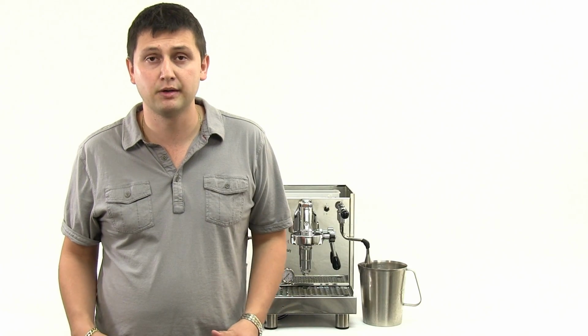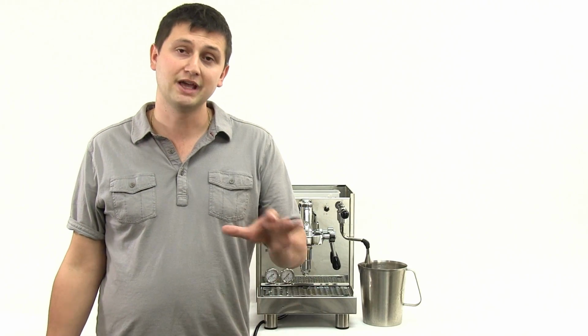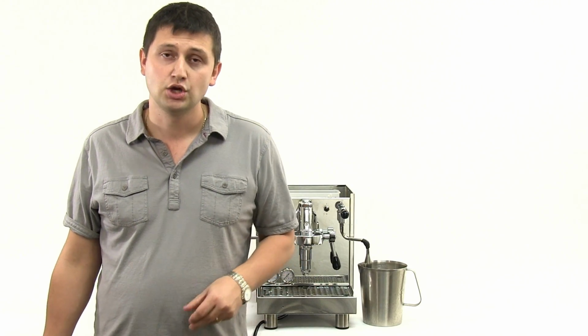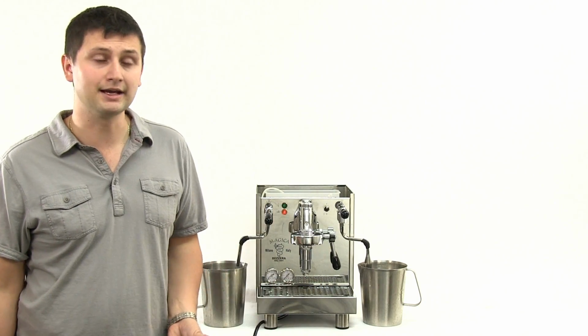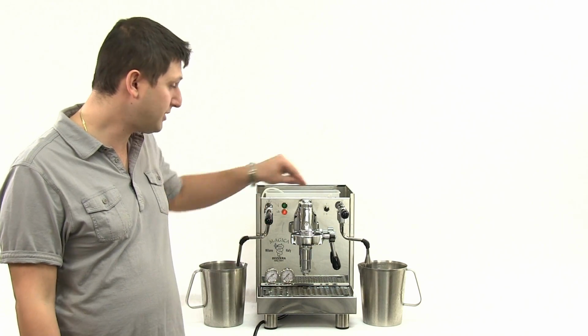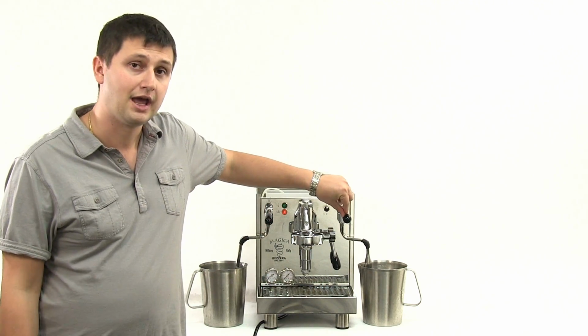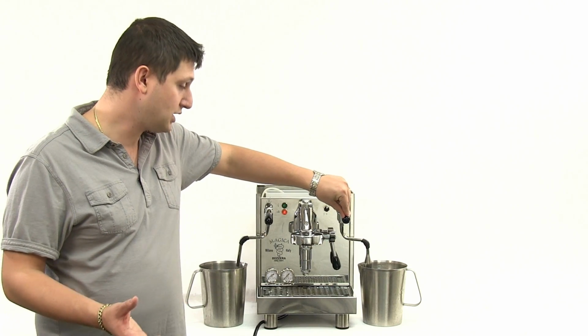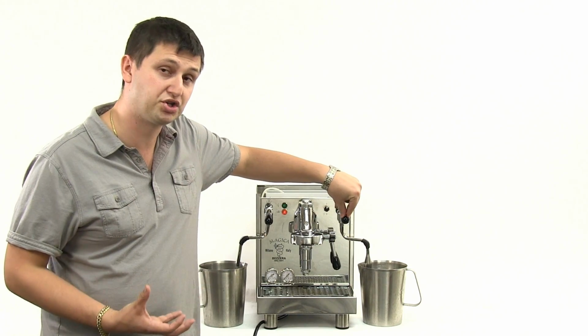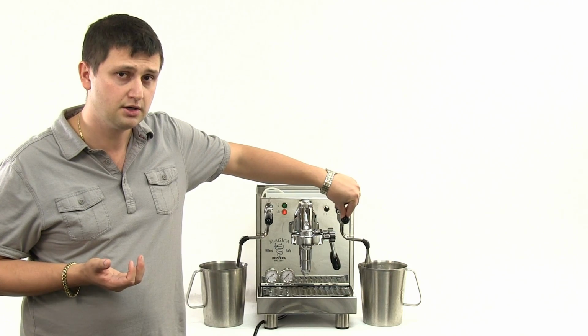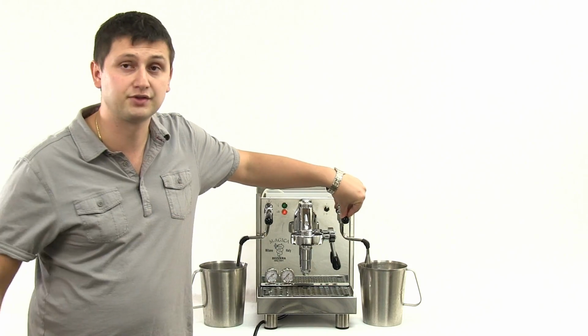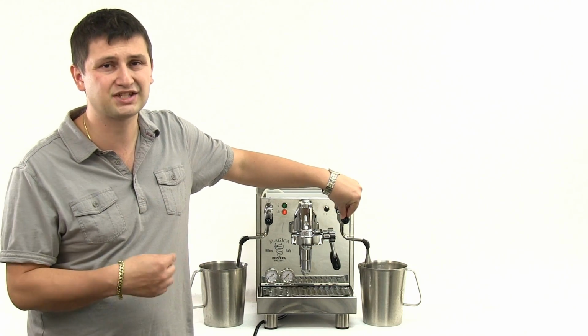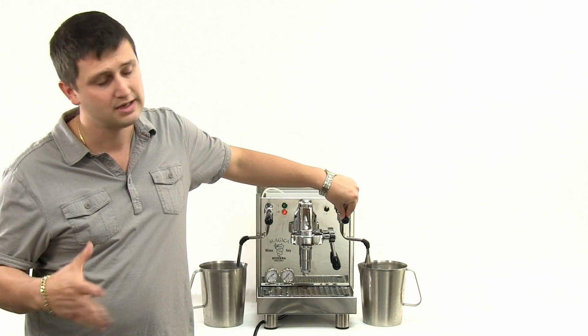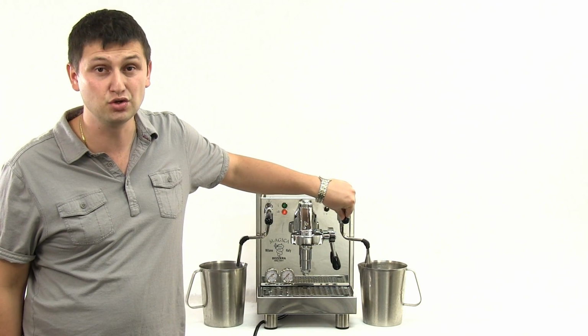Just to return the boiler level back to normal. So again, with your level probe connected, you turn the machine on so it begins heating, and you have your steam and hot water taps open. And as the machine heats, it will basically, using pressure, expel the excess water and return back to the normal level. When you hear the machine ask for water, that means the pump turns on, the machine's back to normal and ready to use.